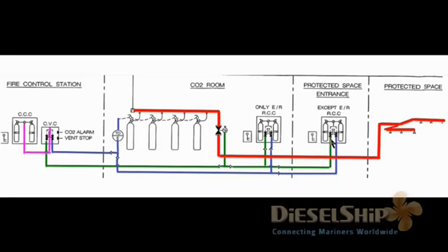So I open the cabinet, confirm everything is stopped and everything is perfect for release of CO2, mustering is done, and the order comes from the captain. The chief engineer operates these two valves. I open the bottle over here, and pressure is indicated. Let's follow the green line now. It goes through the check valve, non-return, and it goes and opens the main distribution valve.